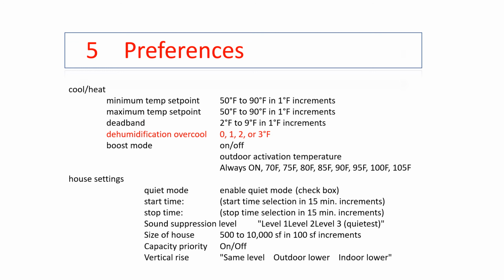We also will see our size of home, which should be used for the IAQ portion, and we'll see vertical rise. The vertical rise will be set in the future. It will monitor where the indoor coil is at. So if it's far below the outdoor unit, it will know it needs to do oil return more often. If it sits above, it'll do the oil return less often.